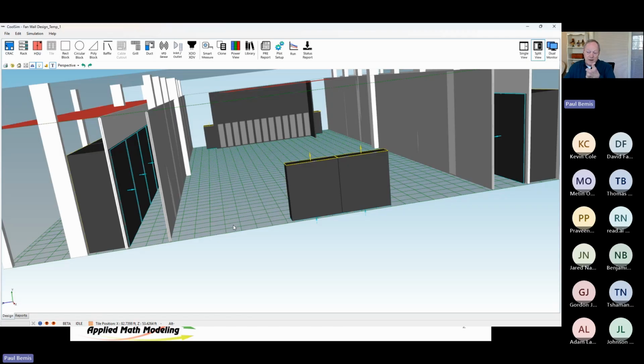You want it to come up out on the edges, particularly the edges of the racks. It won't come up. This is generally how they're doing it these days. These big fan walls. This structure right here is generally a diffuser. That's got some percentage open in it. So this is a screen that they use to try to unify the pressure in the case of N+1.